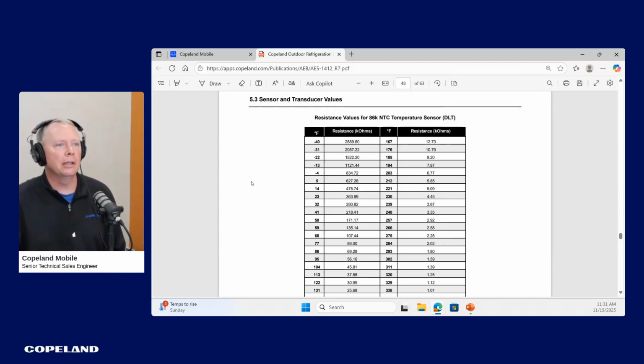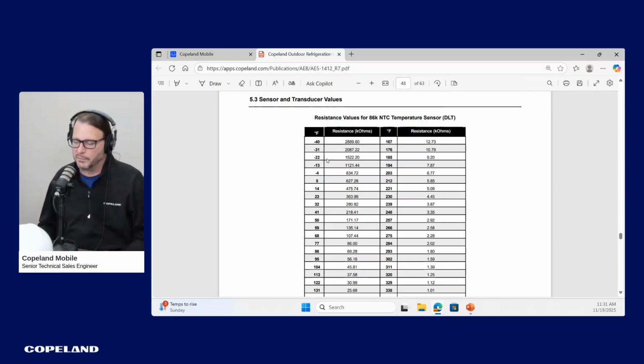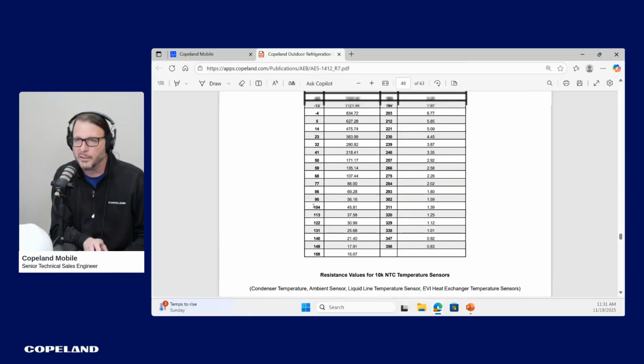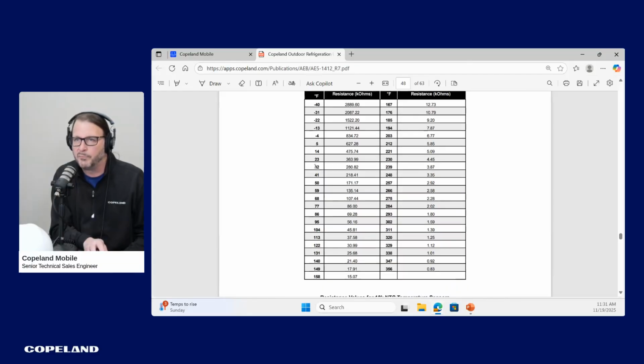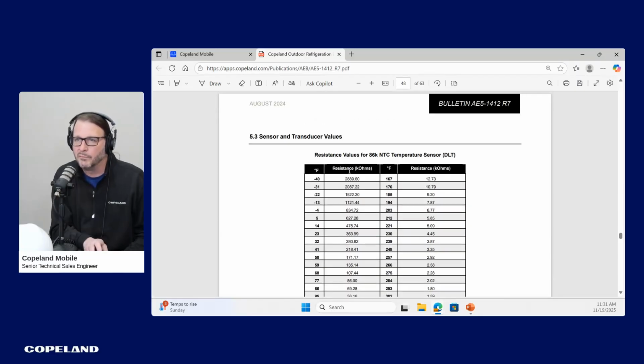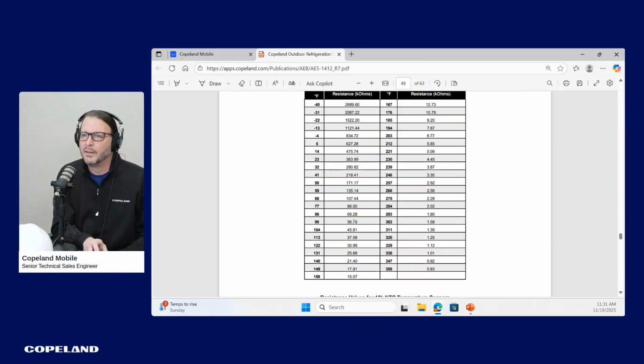It's showing, if you wanted to check this sensor, you would use this temperature in Fahrenheit. What I tell most folks to do, if they'd like to check it, is get a little cup full of ice water and set the sensor in there, use your ohm-meter, and you should get something very near to 280.82 kilo ohms.